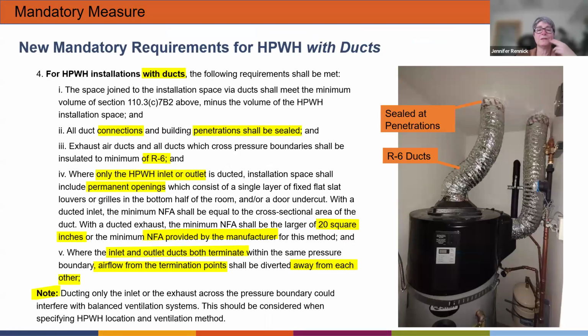But what it really comes down to is that we were seeing a lot of, like, the royal we, but I mean, Grant and I've seen it, and many people that were consulting to the California Energy Commission were seeing it, that there really isn't anything wrong with the heat pump water heater technology, but there are a handful of things people needed to do to make the installation energy efficient, basically to not give heat pump water heaters a bad name because of poor installation.